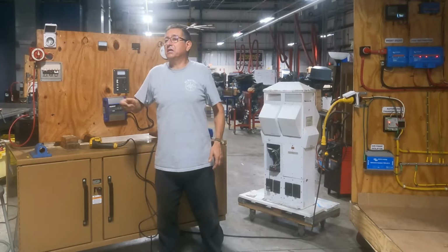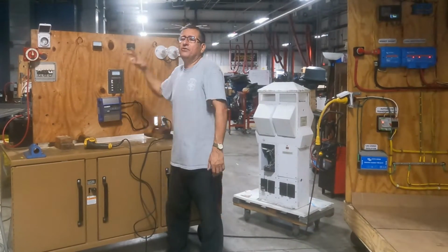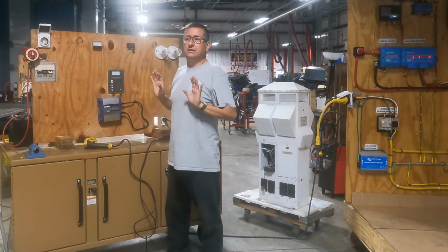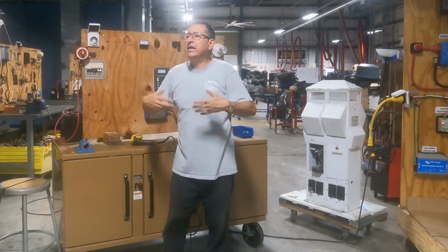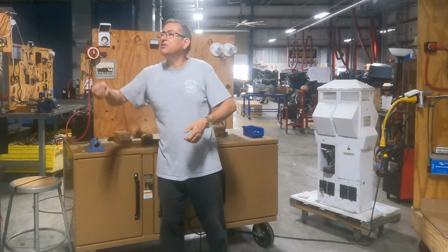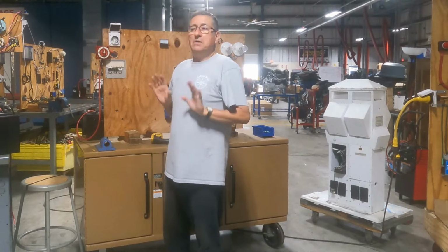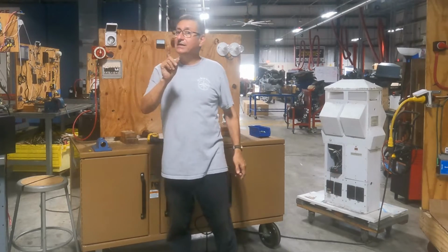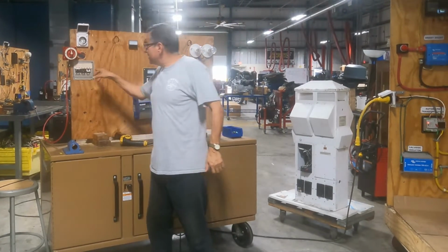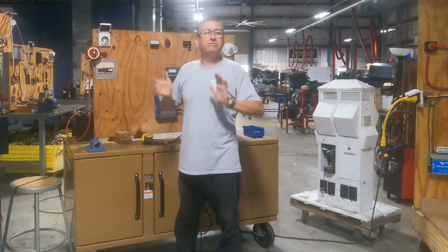I turn off that breaker. And additionally, this breaker is off. It's impossible that power enters here. And if it is? Okay, with that breaker off, I can do the service, and I can start that generator and verify if the output is good, 120, 120. However, the boat is running with shore power. Don't forget that. Because the breakers, this one, and the breaker on the back end, are off.